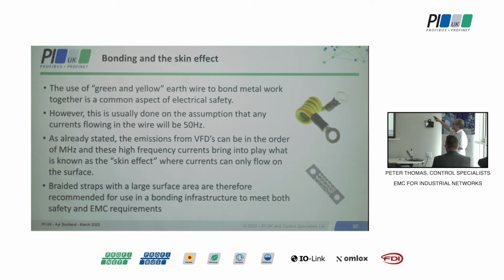So, bonding and the skin effect, this is something else. We've got a normal green and yellow conductor there, often used for bonding bits of metalwork together to form our bonding infrastructure. And there is absolutely nothing wrong with that for 50-60 hertz safety. The problem is that all of the cables for a 50-60 hertz installation are sized for the currents at 50-60 hertz, and I've got nothing new to say about that. And when you are sizing it, you are assuming you have got the full cross-sectional area of the copper to play with. It's just a given that the current flows in all aspects.